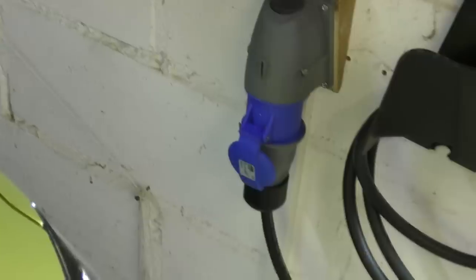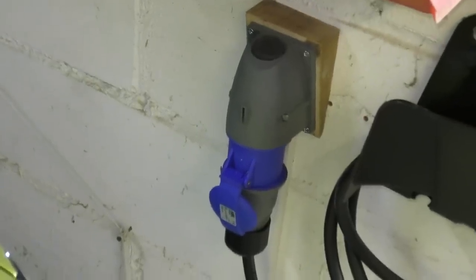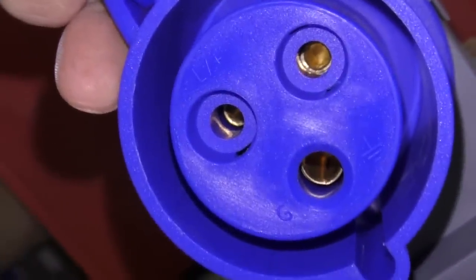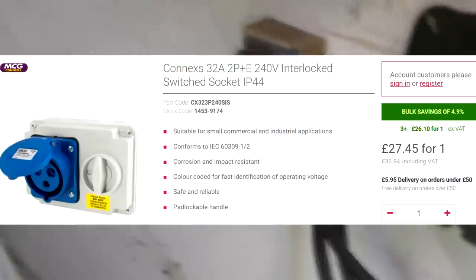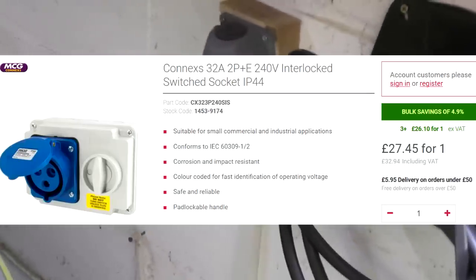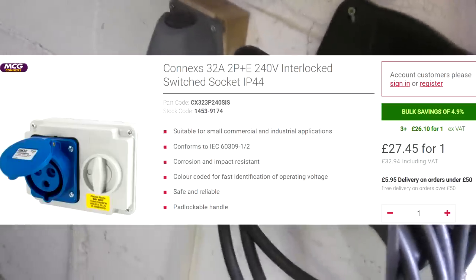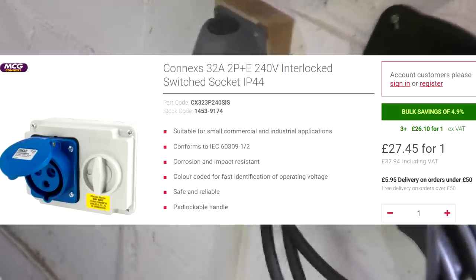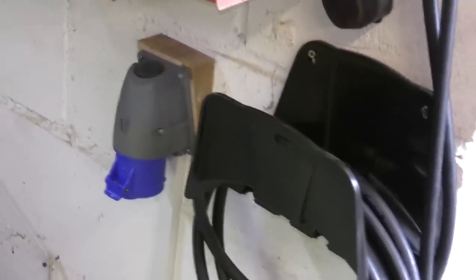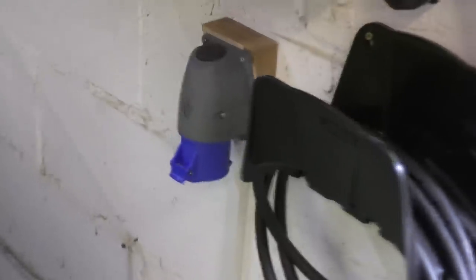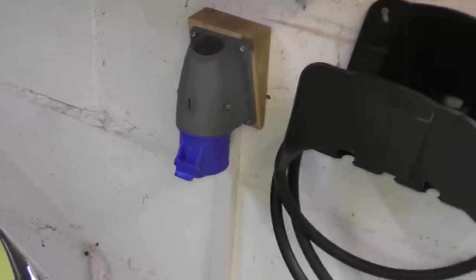Strictly speaking, for a domestic situation, what you should really install is an interlocked socket, because one issue on these sockets is that unlike standard UK 13 amp outlets, there's no shuttering on the connector. So in principle, inquisitive fingers could jab something in there and you'd have mains on there. But you can buy fairly cheaply an interlocked socket. It's basically a socket and a switch in one box, designed so that you can't turn the switch on unless there's a plug inserted, and you can't remove the plug while it's switched on. So for a normal domestic installation, especially if you've got kids around, I definitely recommend that you use an interlocked socket.